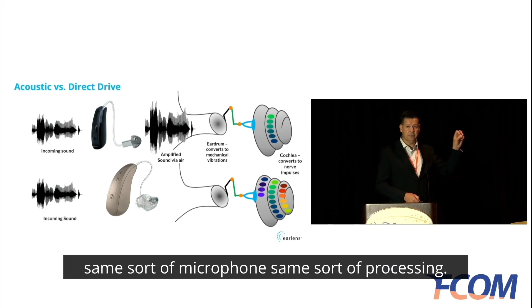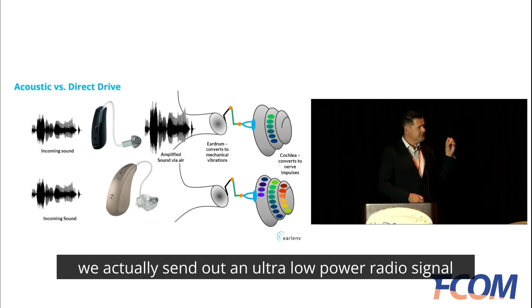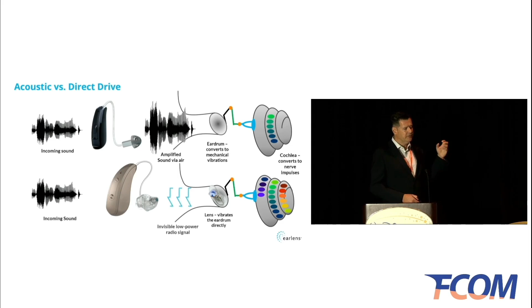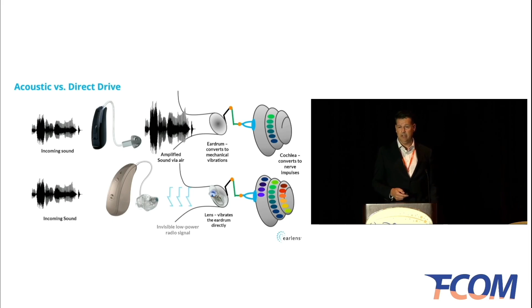Earlens works the same way on the front end. Same sort of microphone, same sort of processing, but rather than produce sound in the ear canal, we actually send out an ultra-low power radio signal from a coil that's in the ear tip. The signal provides both power and audio data to the custom-built transducer that vibrates the umbo of the malleus. And this is able to very efficiently overcome the impedance mismatch between the very springy air and the very stiff eardrum and transmit that energy very efficiently into the middle ear and onwards to the inner ear, providing that extended bandwidth.